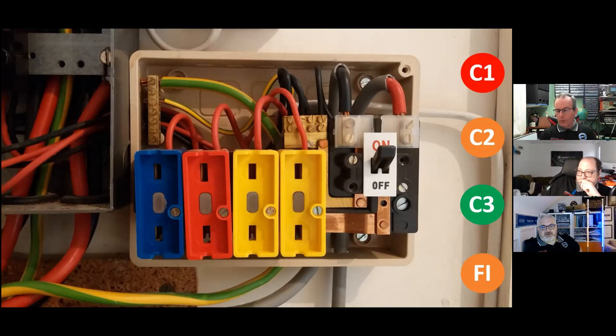Age of installation, CPCs, exposed copper. It's a cumulative narrative, I think, with this. I would suggest that the board is life expired and may not provide sufficient protection for the installation in the event of a single and tragic failure. John, is the equipment on this modern or is it old? I think it was 1970s stuff, and someone's put this in in the 1980s as some kind of replacement for what was in the one to the left of it. It was all ripped out and replaced in the end.